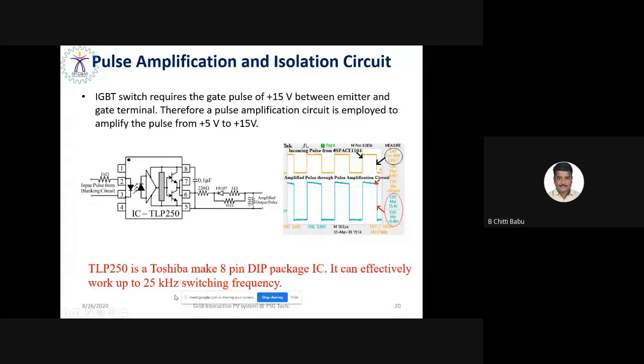That is more than enough, because if you operate at 25 kilohertz, it doesn't mean the speed of response is very good. It implies that as the switching frequency is increasing, again there is a power loss. What is called the switching loss of the voltage source inverter, and again it degrades the efficiency of the system and moreover causes overheating as well. That is one. For most grid connected inverter systems, we design the control circuitry to generate PWM pulses up to 10 kilohertz switching frequency.